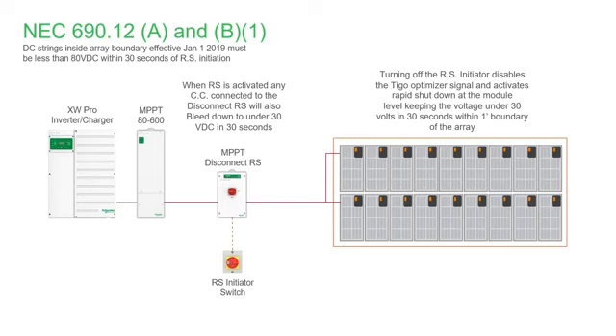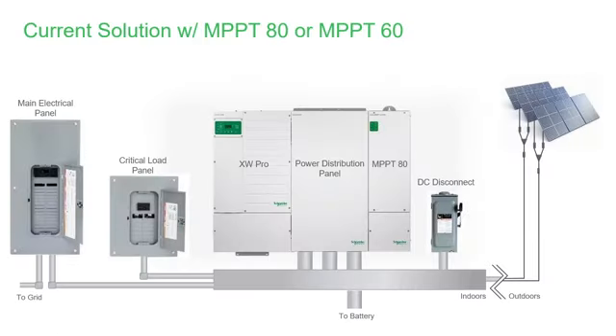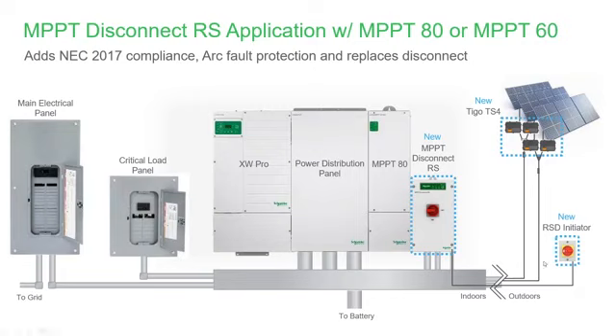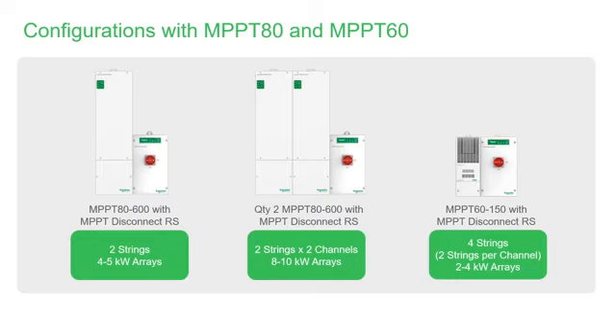This is a little bit more with the architecture where you'll see the inverter and charge controller side by side. Traditionally, we would have a PV disconnect nearby because per code it can't be on the roof, it has to be nearby. And so what we're doing here is replacing that disconnect with the MPPT Disconnect RS. So three things in one: rapid shutdown, arc fault, and PV disconnect. This product, by the way, is also compatible with the MPPT60. Today, I was only talking about the MPPT80, but it is also compatible with the MPPT60. You can have as many as two MPPT80 with one Disconnect RS. So you have one initiator, one Disconnect RS per unit.